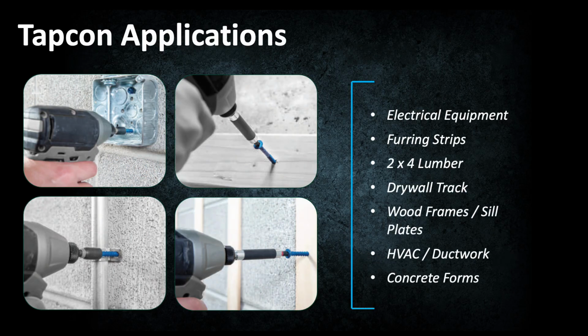Here you can see some of the most common Tapcon applications in the electrical world. Mounting electrical panels and disconnects directly to concrete or block walls, fastening junction boxes and straps, attaching furring strips or wood bucks, and supporting ductwork or equipment bracing. The main advantage is speed and simplicity. Simply drill a properly sized hole, clean it out, and drive the Tapcon to the correct embedment.